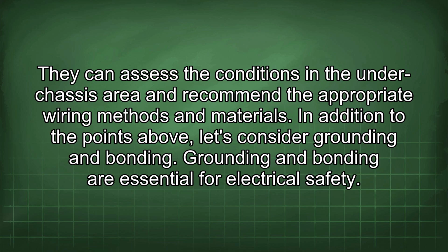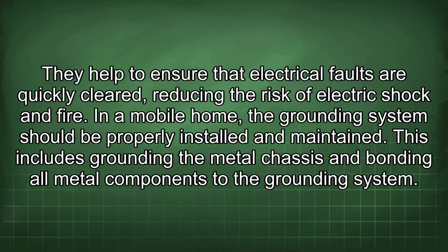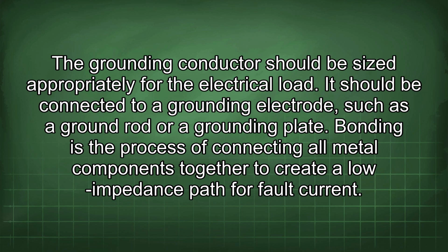In addition to the points above, let's consider grounding and bonding. Grounding and bonding are essential for electrical safety. They help to ensure that electrical faults are quickly cleared, reducing the risk of electric shock and fire. In a mobile home, the grounding system should be properly installed and maintained. This includes grounding the metal chassis and bonding all metal components to the grounding system. The grounding conductor should be sized appropriately for the electrical load. It should be connected to a grounding electrode, such as a ground rod or a grounding plate.